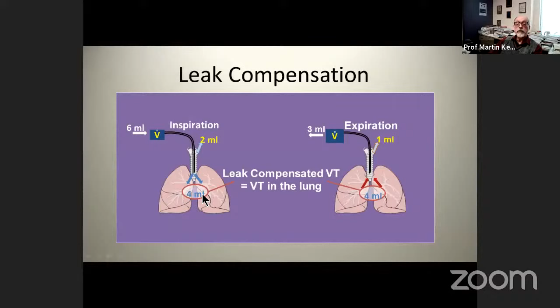So this is a really important advance, and it's an option. You can activate it or not. If you don't use the automatic leak compensation, which you should, if you don't use it and you have a large leak here, it's a very large leak, but that's for illustration purposes, your exhaled tidal volume is going to be measured at 3.6, and the tidal volume per kilo is tiny, would be inadequate. You would be worried, and you see the leak here. So the tidal volume without leak compensation is the measured exhaled tidal volume, and that's what's used here.